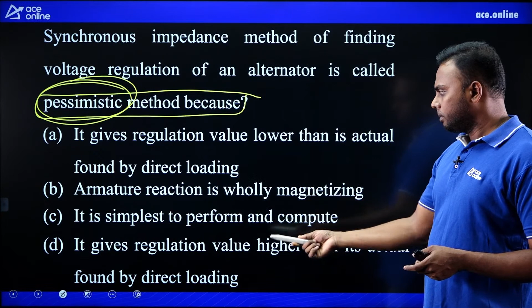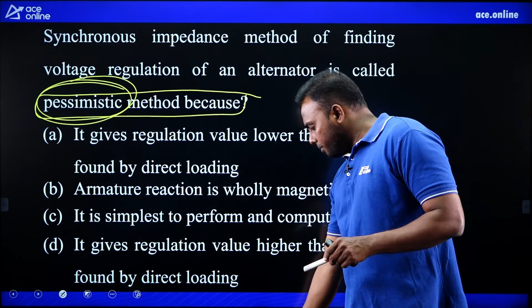Now, the synchronous impedance method of finding voltage regulation of an alternator is called pessimistic - why? Because it gives high regulation? Or does it give a lower value? Is armature reaction wholly magnetizing? Or is it simple to perform? No - it gives a regulation value higher than its actual regulation. That's why we call it pessimistic.